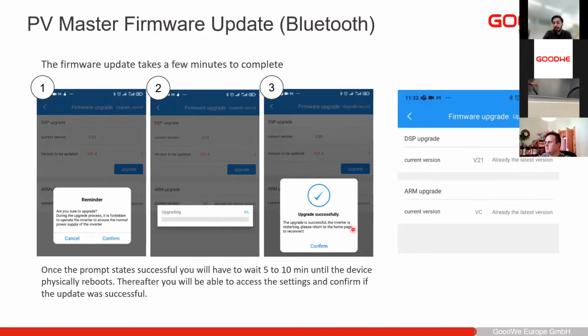And here it says upgrade successfully, then you press confirm, and then you need to wait 5 to 10 minutes until the firmware has been applied successfully. So likely the screen will freeze, and sometimes you might think, okay, it's not really working, but please wait 5 to 10 minutes, and then you will see that the inverter physically reboots. You will see some flashing lights, and that will show you that the reboot and upgrade has been done successfully. And then you will also be able to use the PV Master screen as well and navigate that.